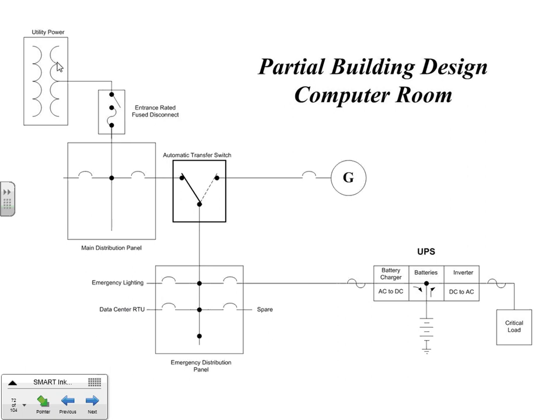And the way this operates, under normal circumstances, the utility comes through the main distribution panel. It has a feeder breaker through the switch to the load, feeds the emergency panel, and the UPS to the critical. When the power fails, transfer switch sensors will see that it's gone, start the generator, bring it up to speed and frequency. When it's there, the switch will see the power here, switch over, and the generator is supplying load to the emergency distribution panel only. Again, way out here in the critical load, it doesn't know anything happened. That make sense?